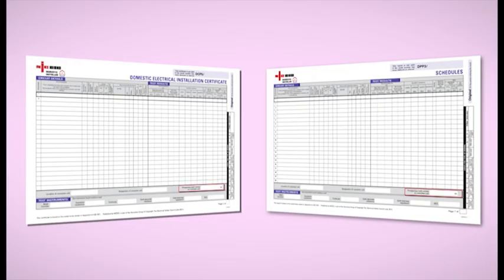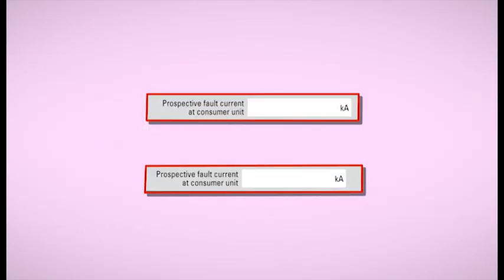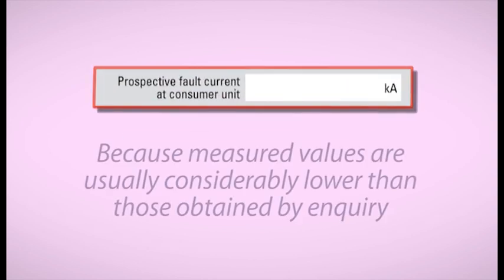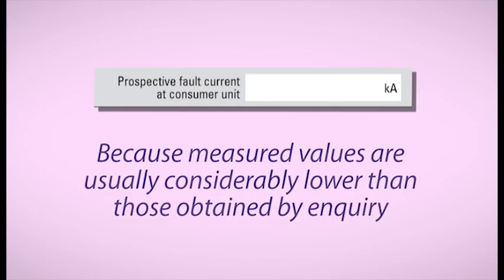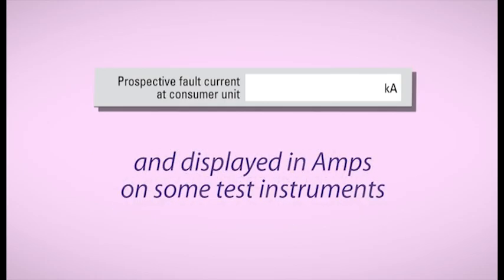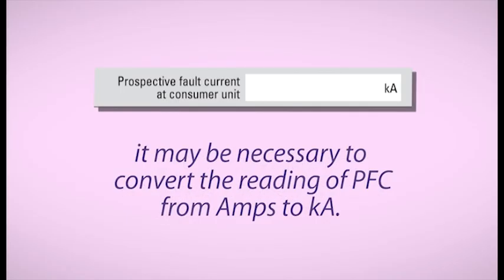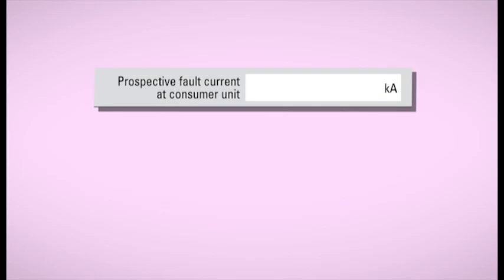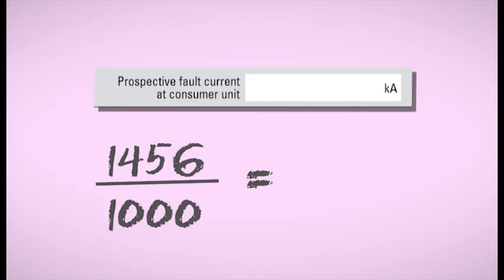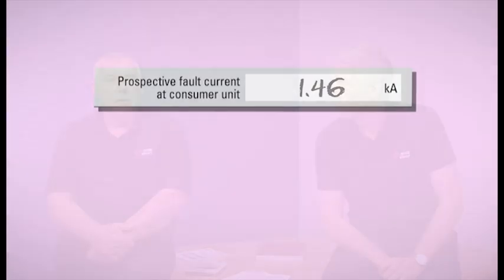On the EICR and domestic EIC forms, there's an additional box under test results for the actual measured value of prospective fault current. Because measured values are usually considerably lower than those obtained by inquiry and displayed in amps on some test instruments, it may on occasion be necessary to convert the readings of PFC from amps to kiloamps. This can be done by dividing by 1000. So for example, 1456 amps becomes 1.46 kA.